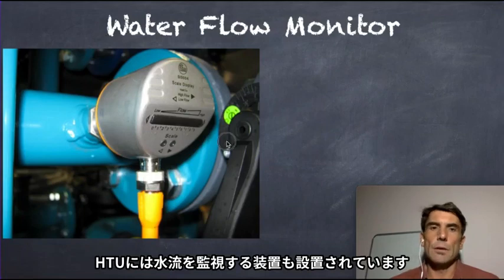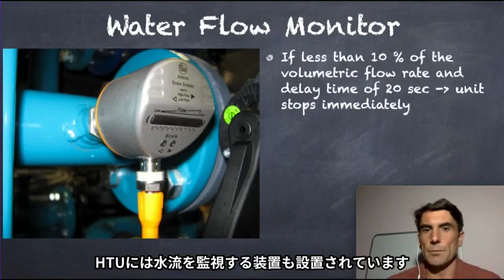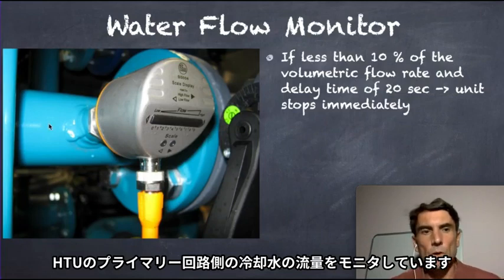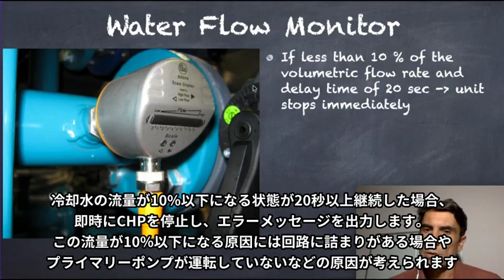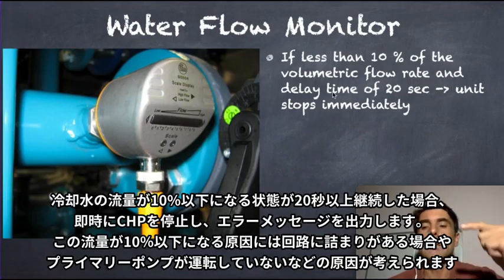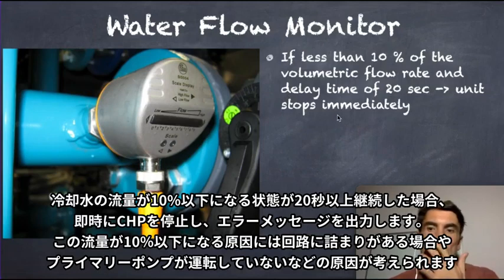In our HTU we have a water flow monitor sensor. This sensor measures the flow through the pipe in the primary circle of the HTU. If the flow is lower than 10%, then either we have problems with our dirt trap, so that the flow cannot circulate through this cycle properly, or the primary pump is not working properly. If the flow rate is below 10% for longer than 20 seconds, there's a delay on the signal, then the CHP will stop immediately with the flow error message.